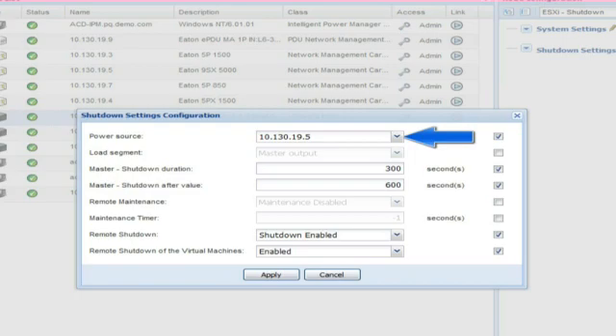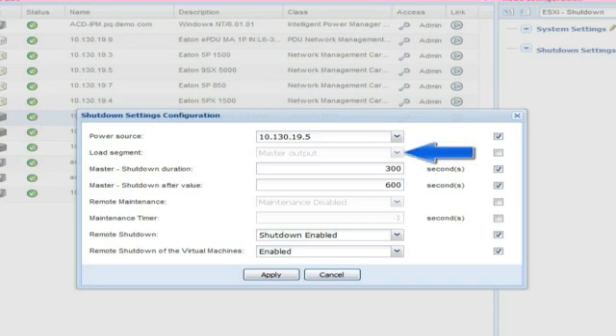Power Source: Select the IP address on the UPS which powers your host. Load Segment: Designate the output receptacle which the host node is connected to the UPS. Typically, this will be the master segment.